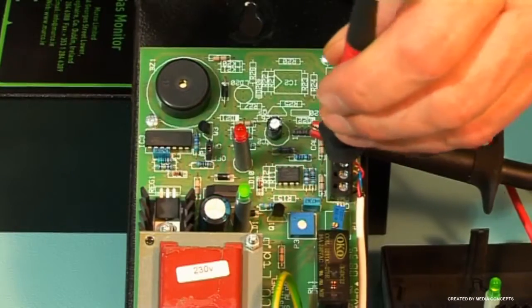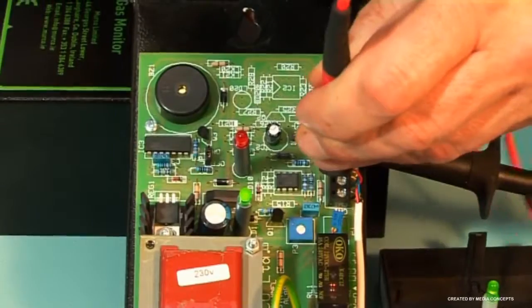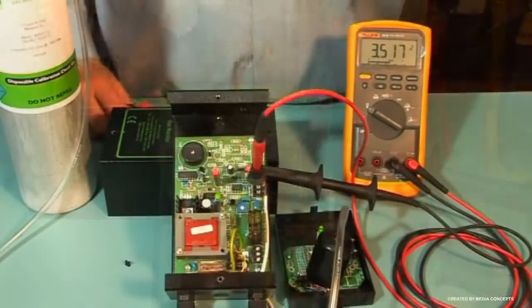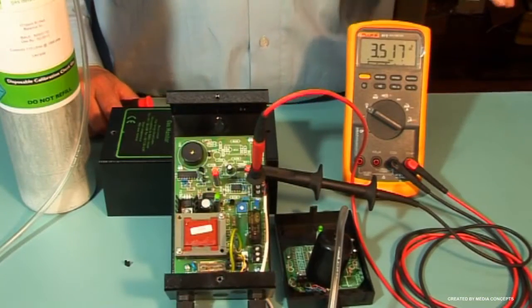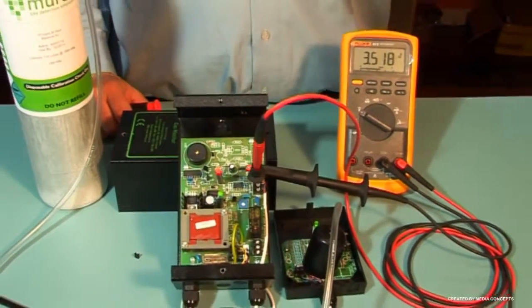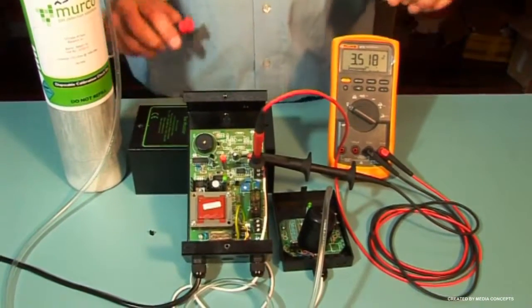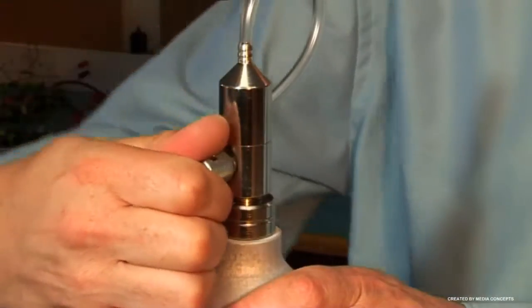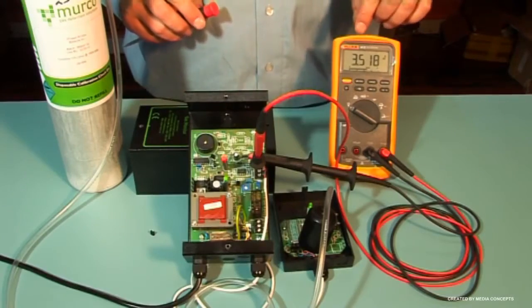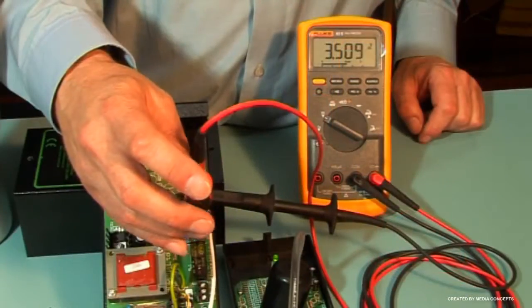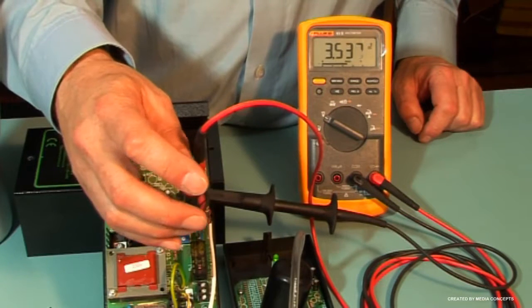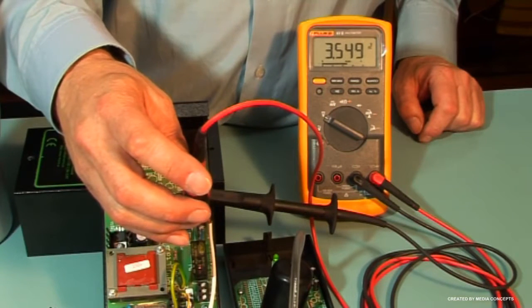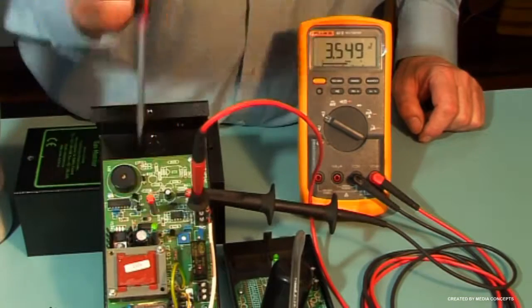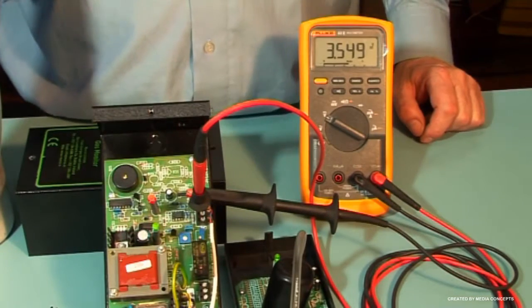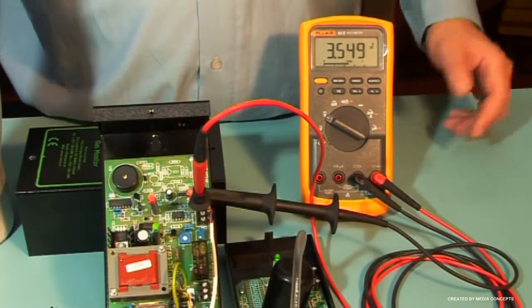Having carried out the electrical setup and with the voltmeter connected between pin 4 on the CAL header and pin 2 on the CN1, with your known target gas and desired range, expose the sensor to the gas and allow the standby voltage to climb. Once the voltage stops climbing and stabilizes, adjust P1 until it is in alarm, approximately 50 millivolts above the alarm set voltage. The MGD will now be in alarm and the relay should activate.